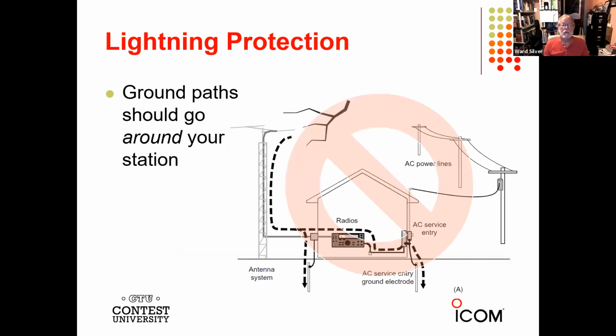Okay, here's an example of lightning protection and where the ground path should go. The ground path should go around your station. This is what not to do. You've got a tower outside, lightning either hits it or gets close to it, current flows down the tower. Remember I told you about the inductance and voltages. So here comes the lightning current. It comes up to this nice entry panel that you built.